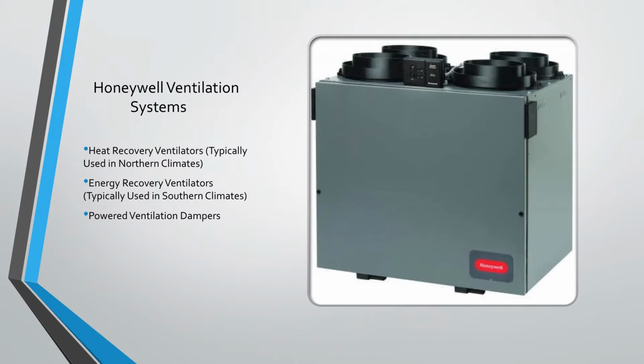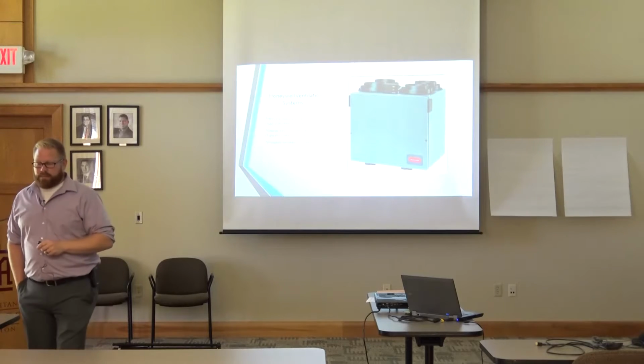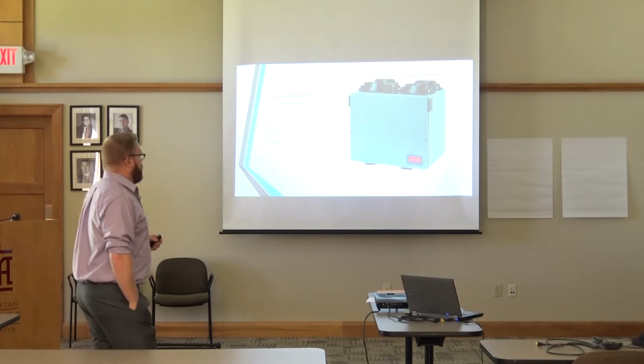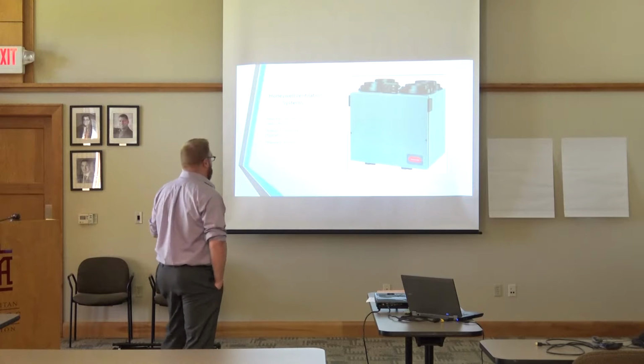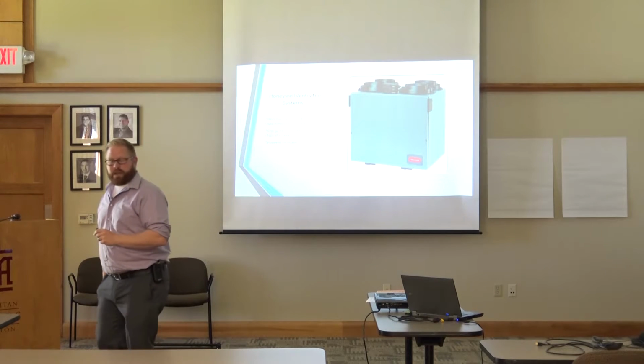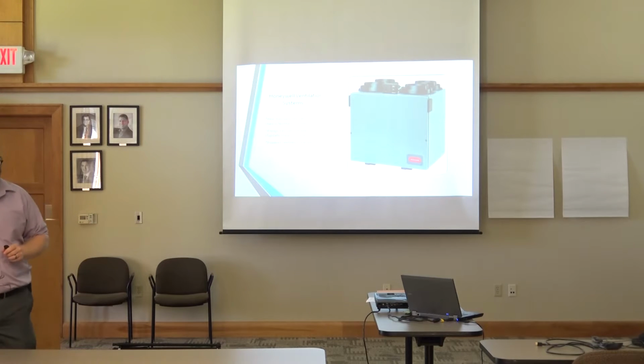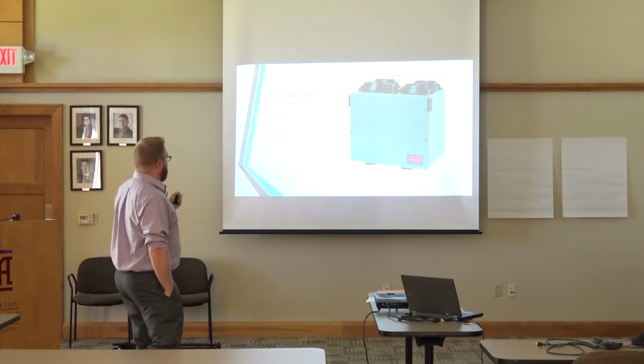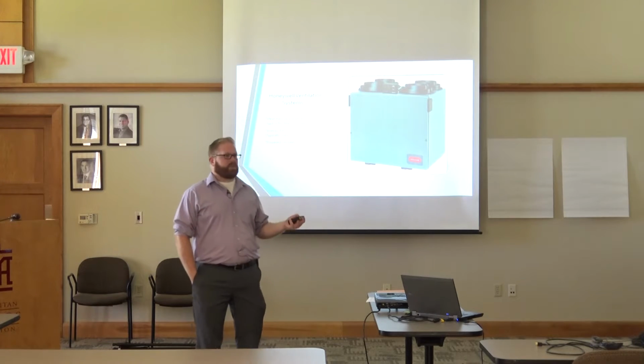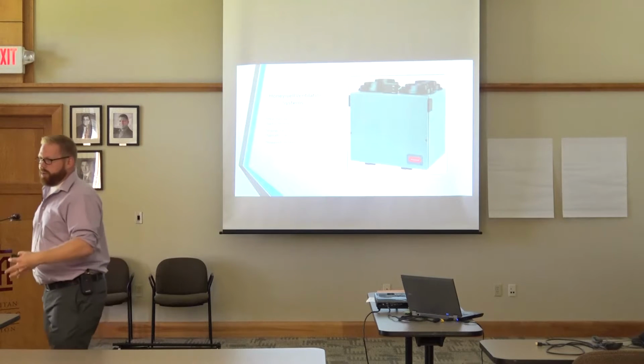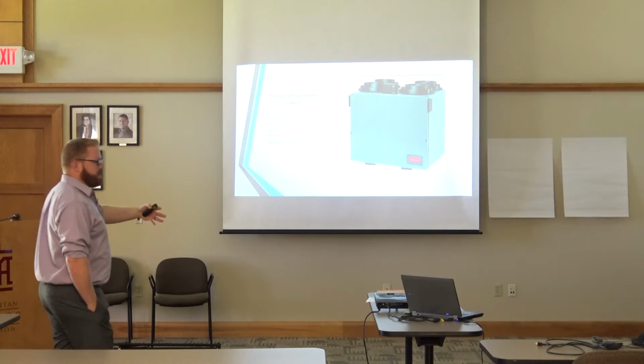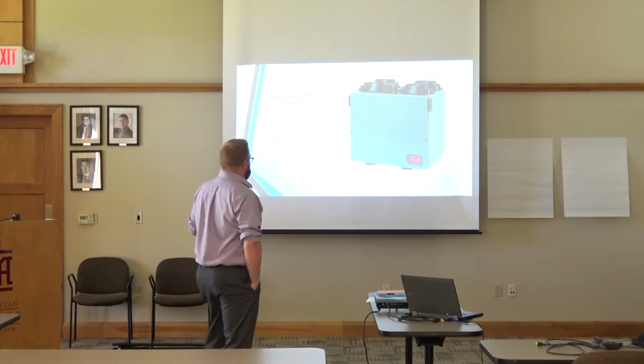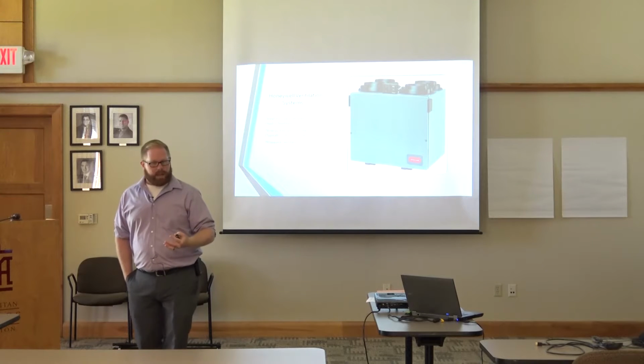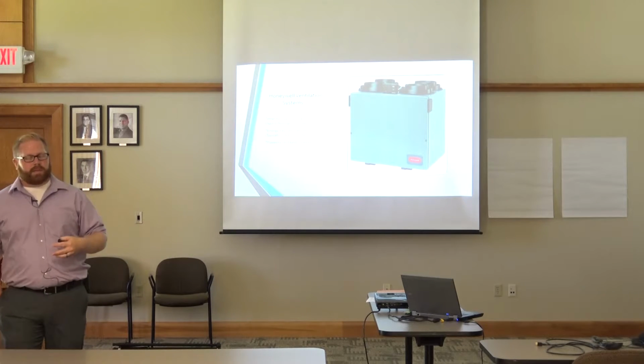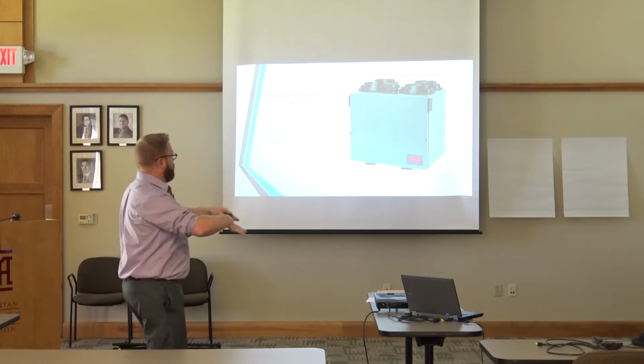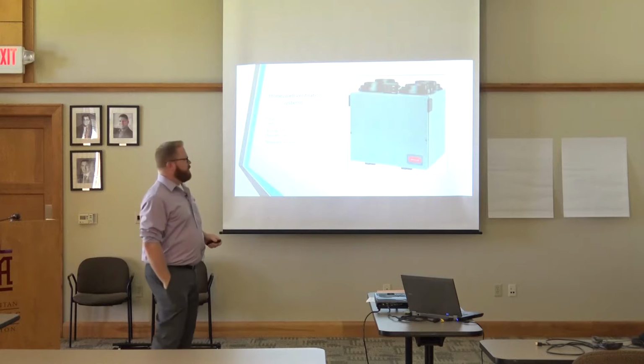One of the last things here is ventilation systems. I know the question was asked whether makeup air or a Scuttle fresh air makeup is used. Another way to tackle ventilation in a house is with an HRV, heat recovery ventilator, or an ERV, energy recovery ventilator. Heat recovery ventilators are typically used in more northern climates, like Wisconsin, because our heating season is longer than our cooling season, and that affects how they exchange and recover heat. ERVs are typically used in southern climates, which are better for dehumidification properties, based on how their internal core exchanges air.